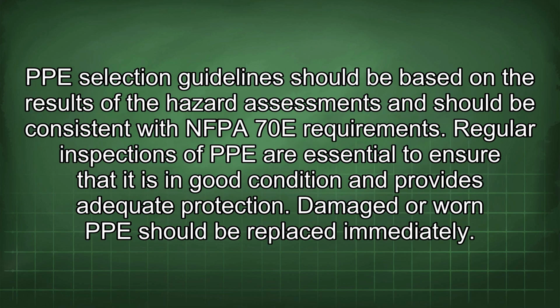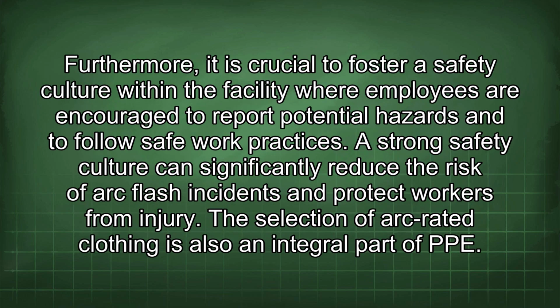PPE selection guidelines should be based on the results of the hazard assessments and should be consistent with NFPA 70E requirements. Regular inspections of PPE are essential to ensure that it is in good condition and provides adequate protection. Damaged or worn PPE should be replaced immediately. Furthermore, it is crucial to foster a safety culture within the facility where employees are encouraged to report potential hazards and to follow safe work practices. A strong safety culture can significantly reduce the risk of arc flash incidents and protect workers from injury.